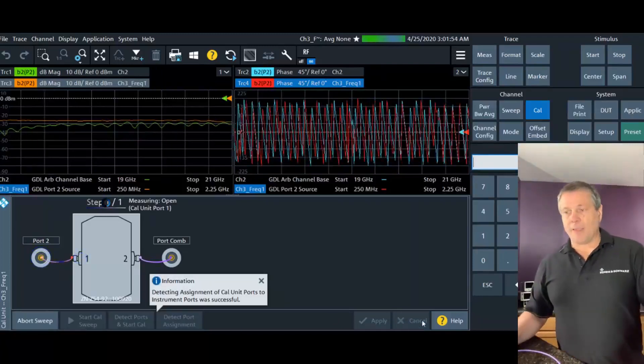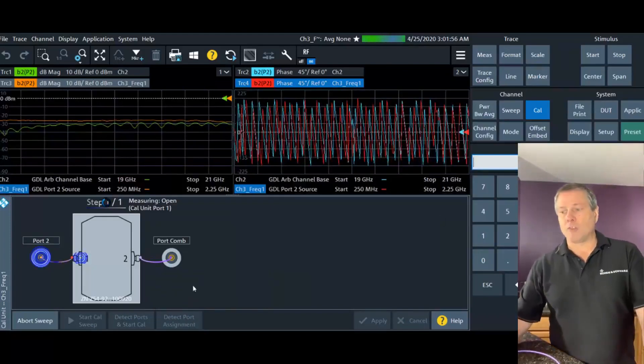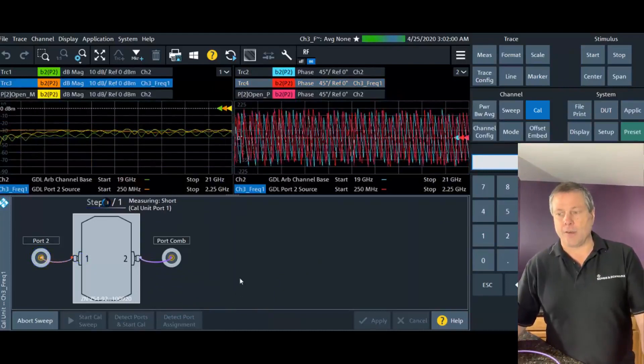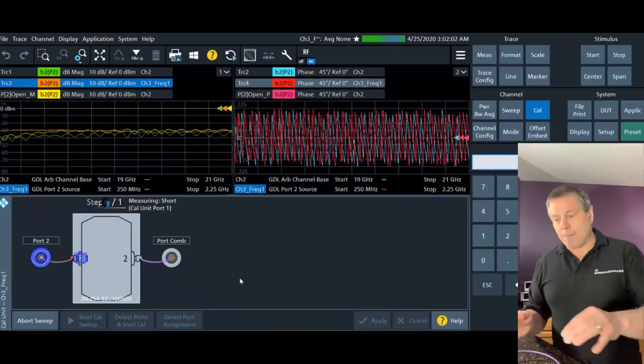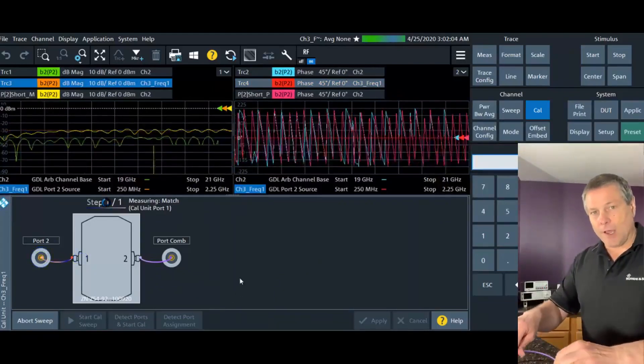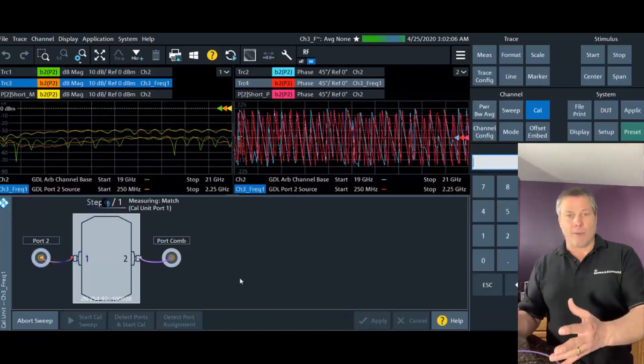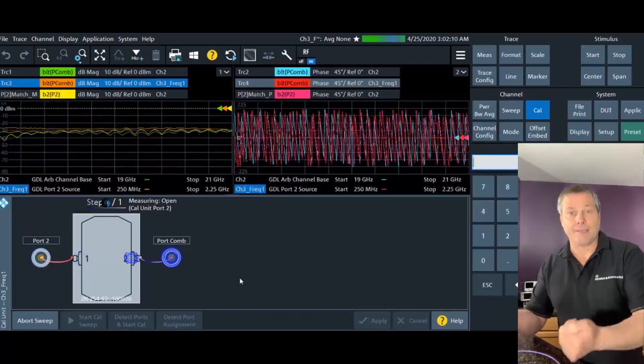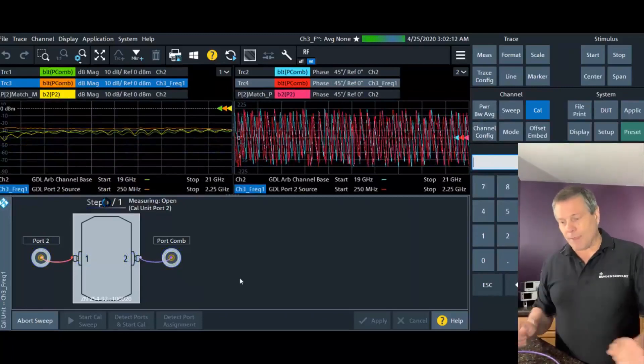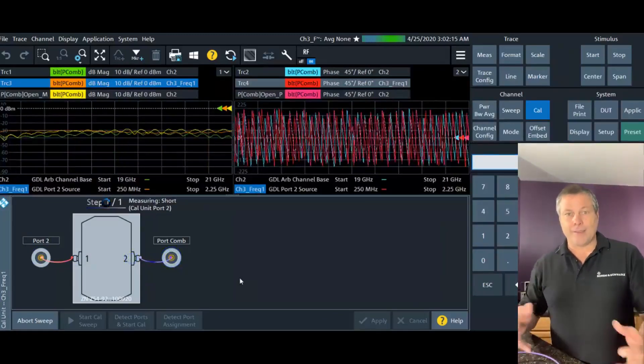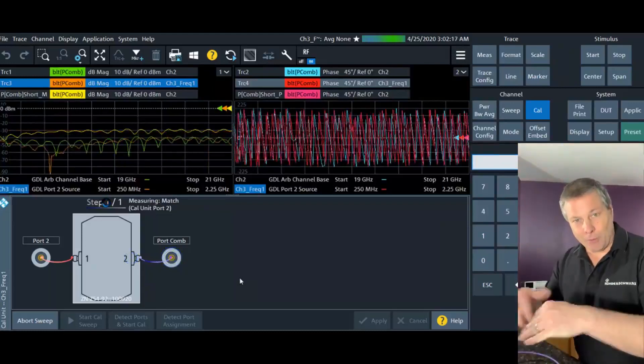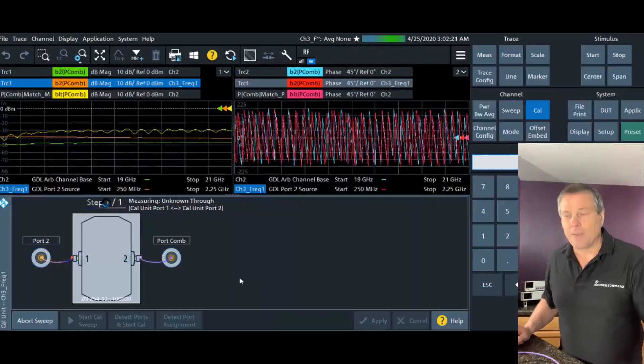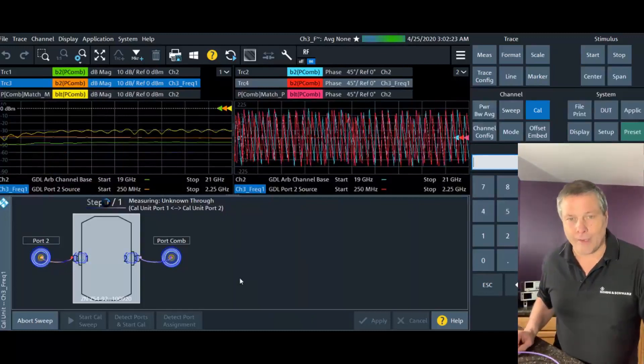A couple of things to point out: I almost always press 'Detect Ports and Start Cal' instead of just 'Start Cal.' The reason is that if I mix up how I've connected the cables to the AutoCal, the Detect Ports button will go out, find out what I did, and automatically adapt to it. So if I ever swap cables by accident, that button will correct for it automatically. There's almost no drawback to doing it — the only time I don't press it is if I accidentally aim at the other button.